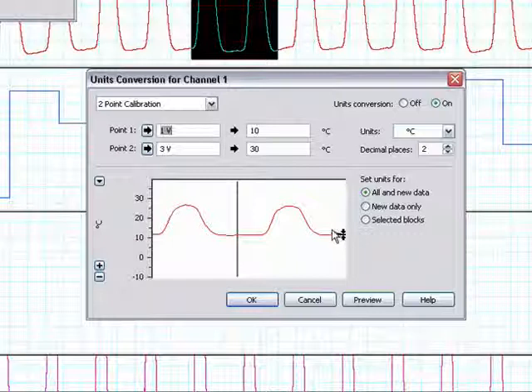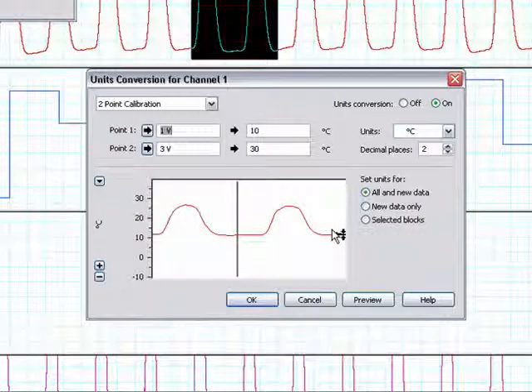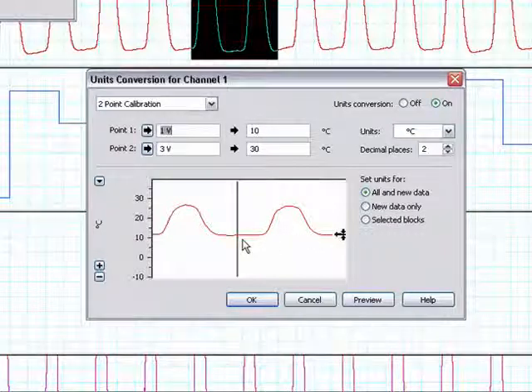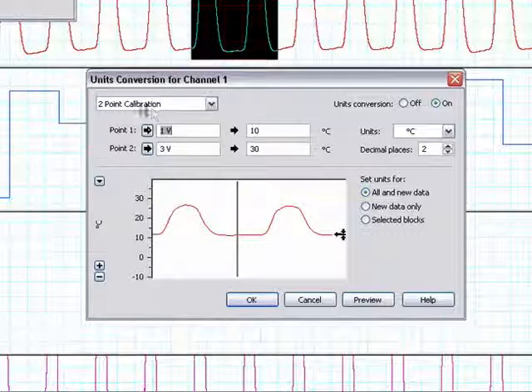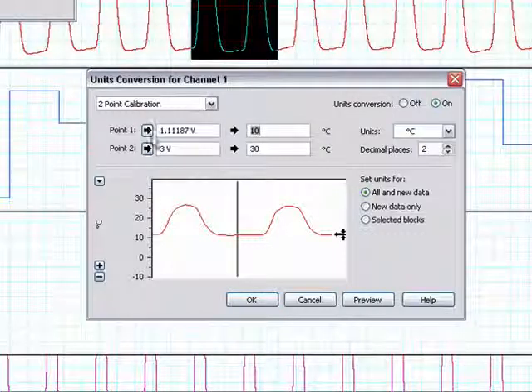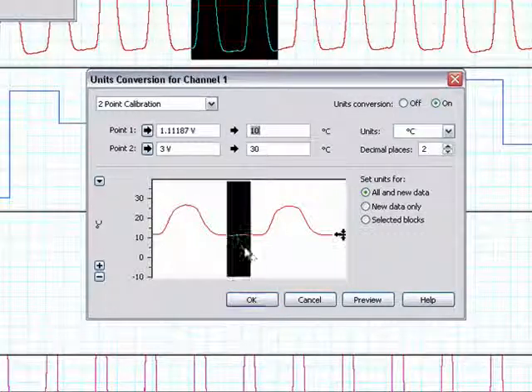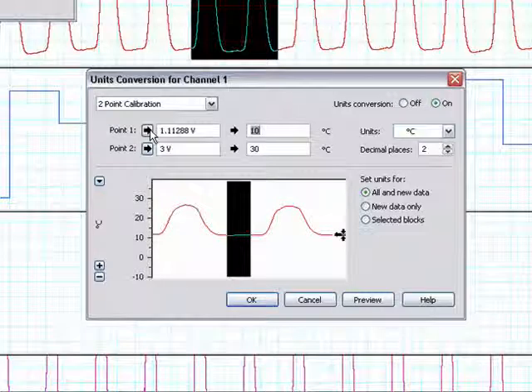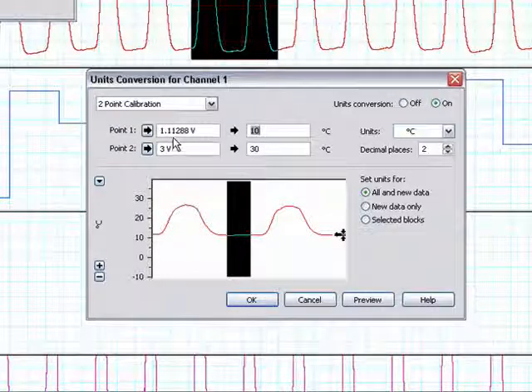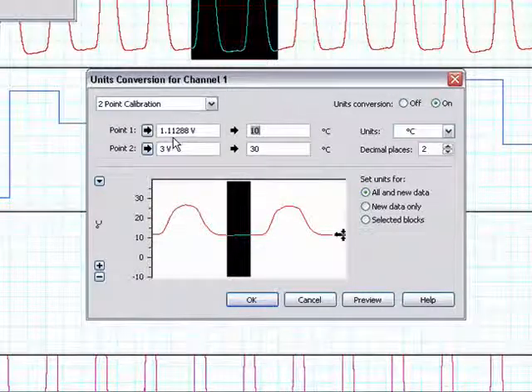If there is a selected point or area in the data display, then clicking the value button enters the voltage value for a single-point selection, or the average voltage for a selection. It is recommended to always take a selection when doing a two-point calibration.